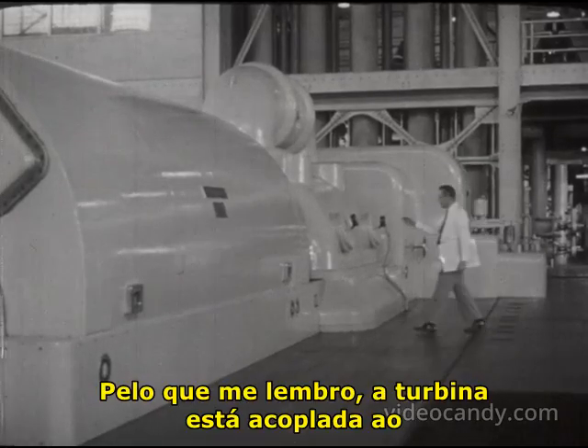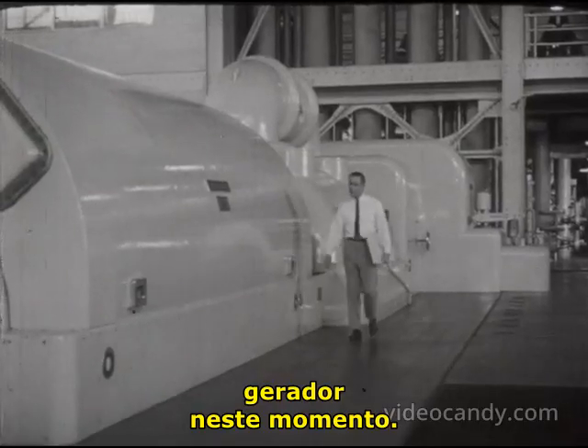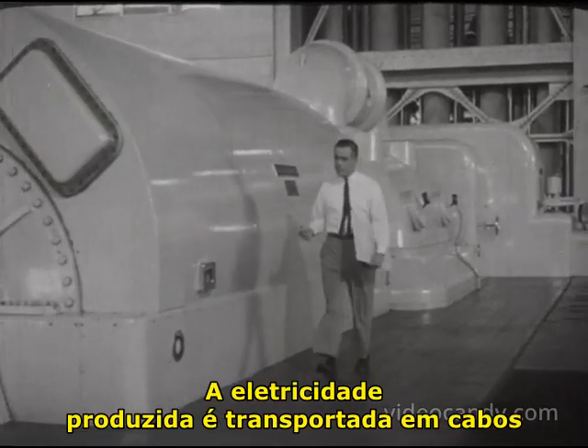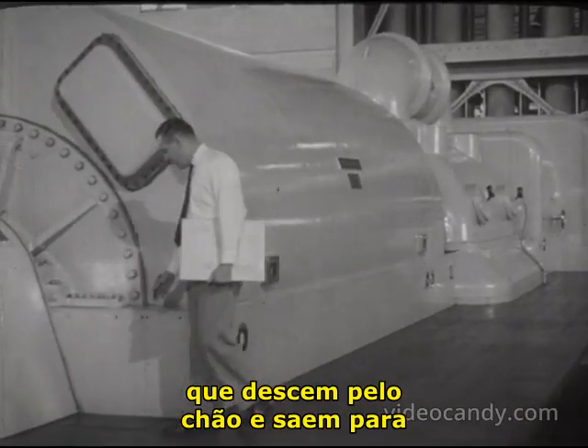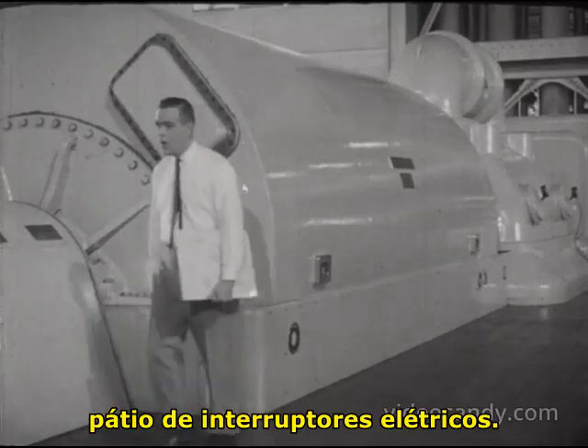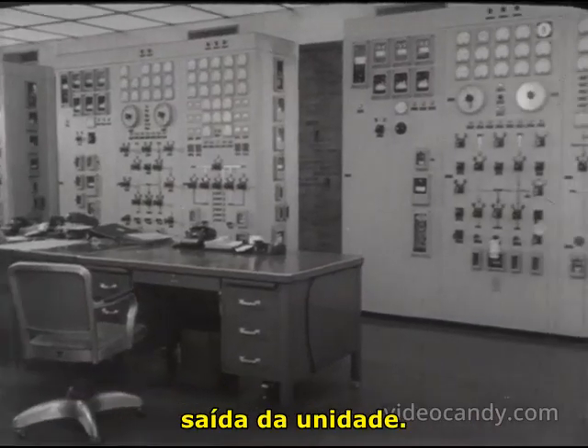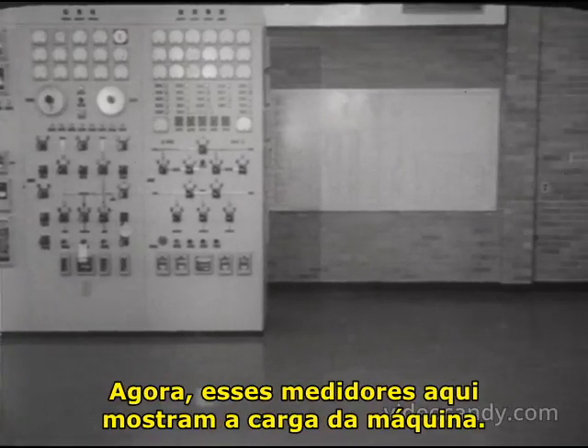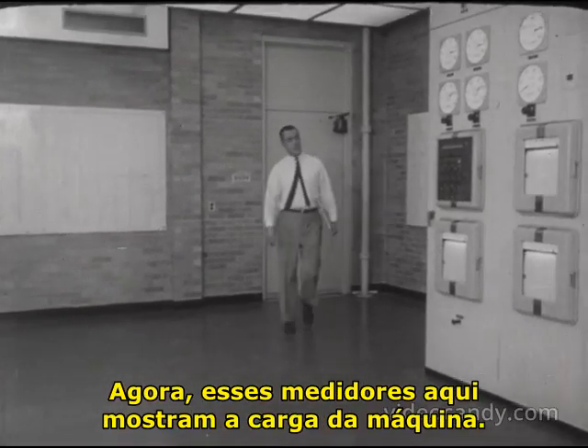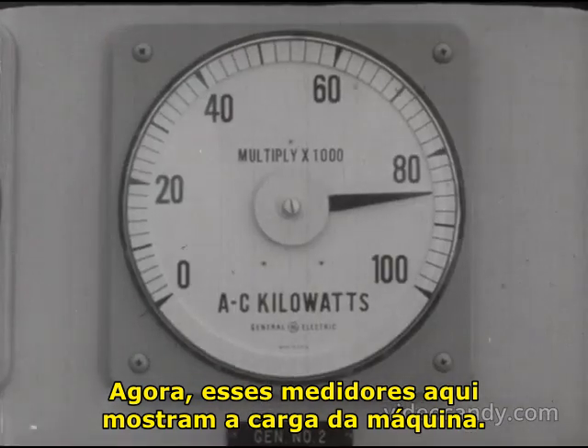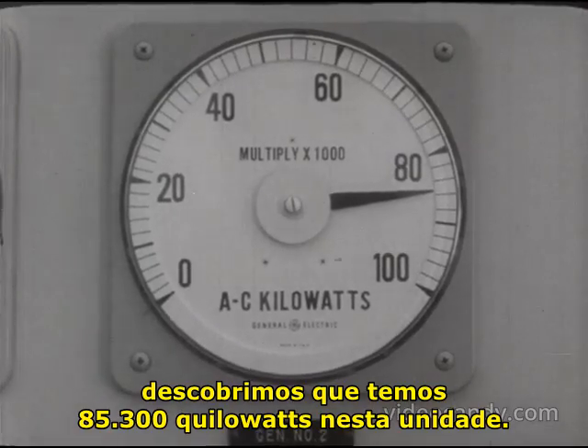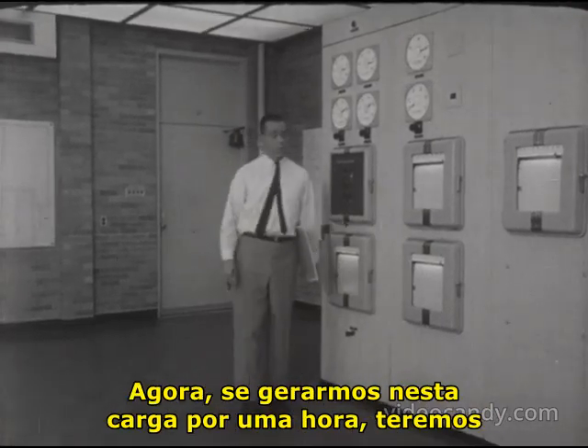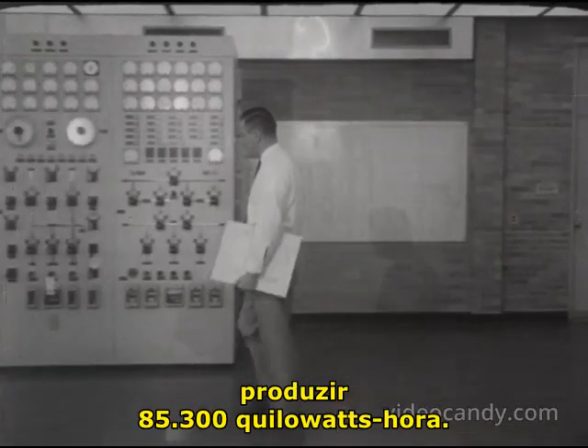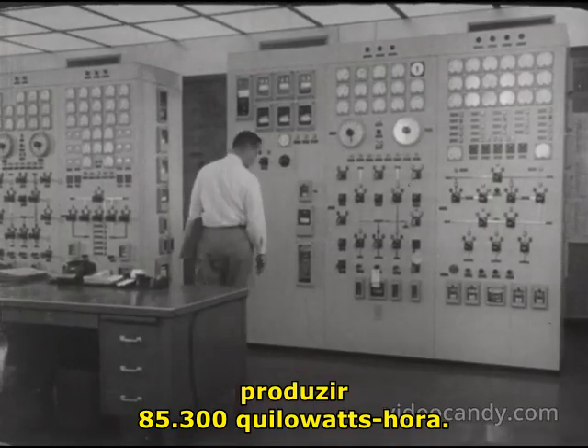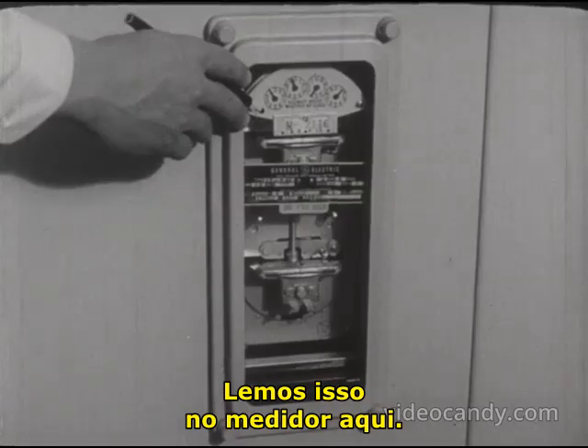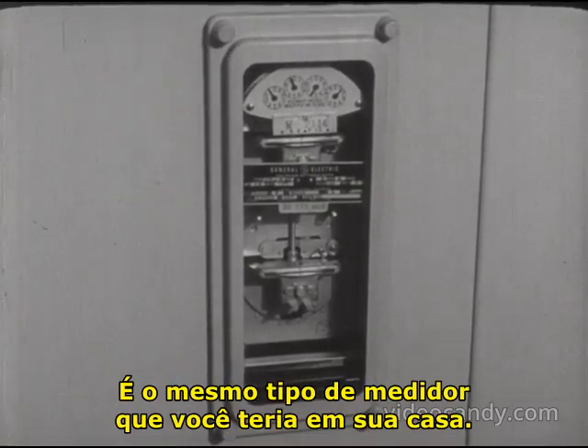Now remember, the turbine is coupled to the generator at this point. The electricity produced is carried away on cables which pass down through the floor out to the electrical switchyard. Over here in this room, we monitor the electrical output of the unit. Now these meters over here show the load on the machine. We find that we have 85,300 kilowatts on this unit. Now, if we generate at this load for 1 hour, we will produce 85,300 kilowatt hours. We read that on this meter here. It's the same kind of a meter you would have in your home.